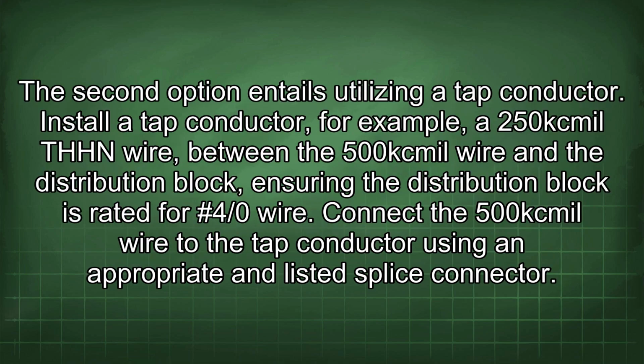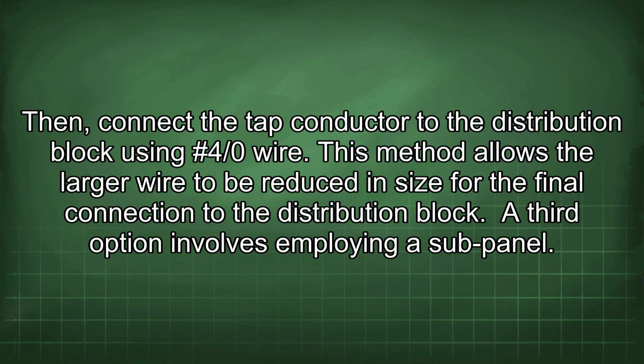The second option entails utilizing a tap conductor. Install a tap conductor, for example, a 250 kcmil THHN wire, between the 500 kcmil wire and the distribution block, ensuring the distribution block is rated for #4/0 wire. Connect the 500 kcmil wire to the tap conductor using an appropriate and listed splice connector. Then, connect the tap conductor to the distribution block using #4/0 wire. This method allows the larger wire to be reduced in size for the final connection to the distribution block.